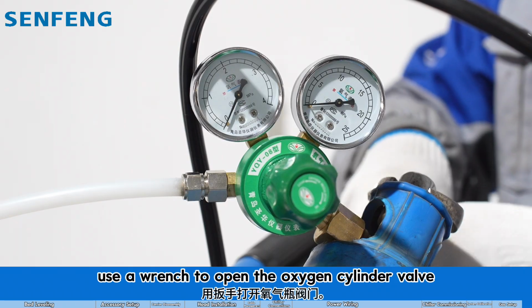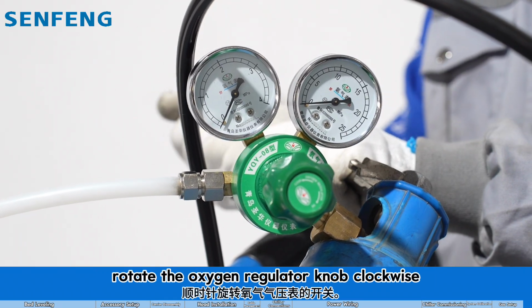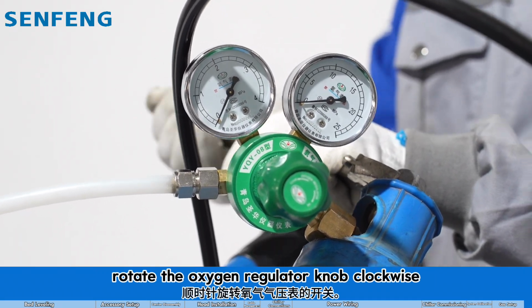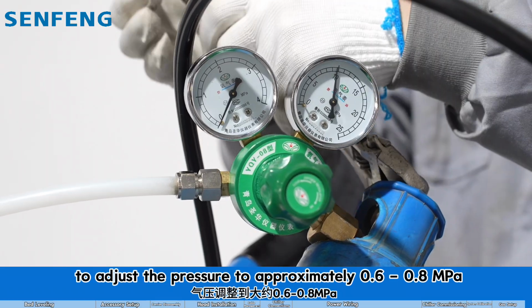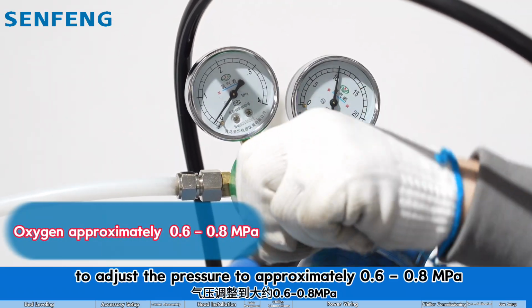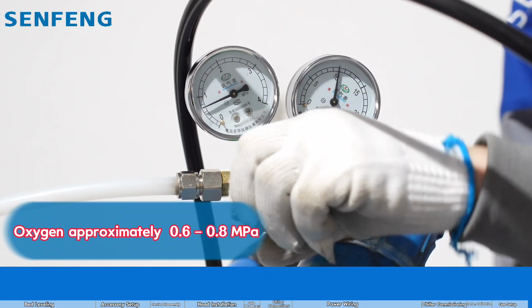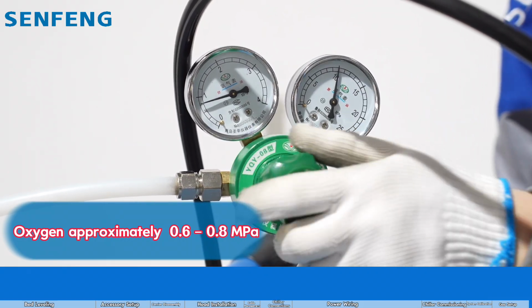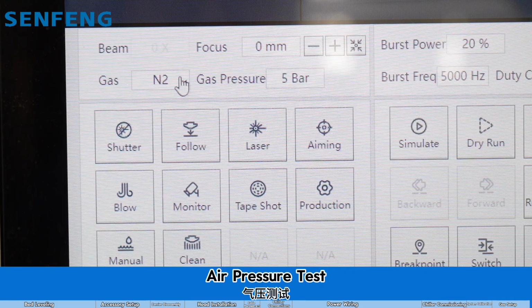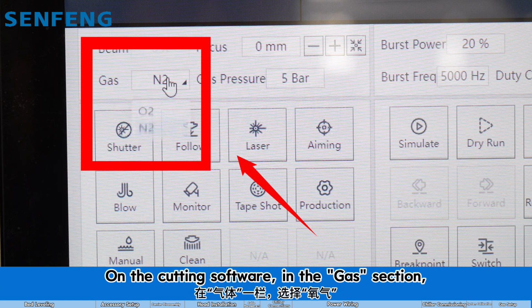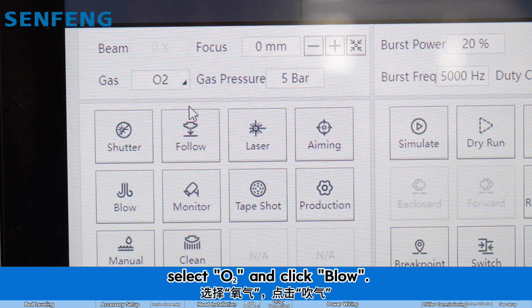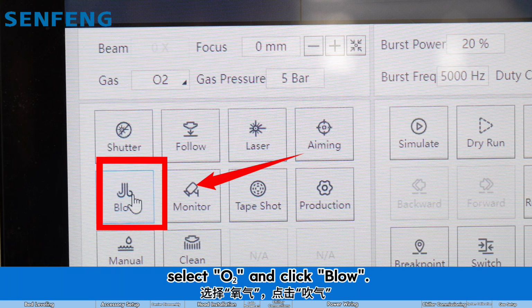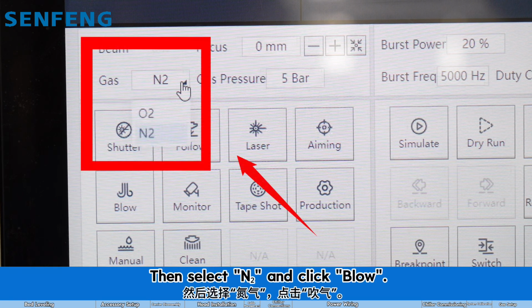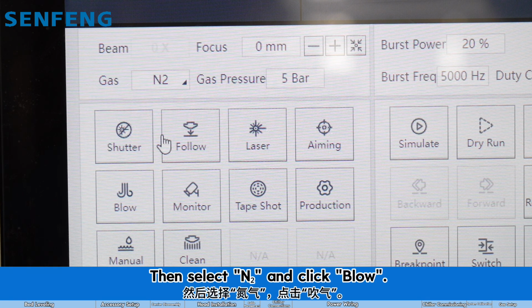Use a wrench to open the oxygen cylinder valve. Rotate the oxygen regulator knob clockwise to adjust the pressure to approximately 0.6 to 0.8 megapascal. Air pressure test. On the cutting software, in the gas section, select oxygen and click blow. Then select nitrogen and click blow.